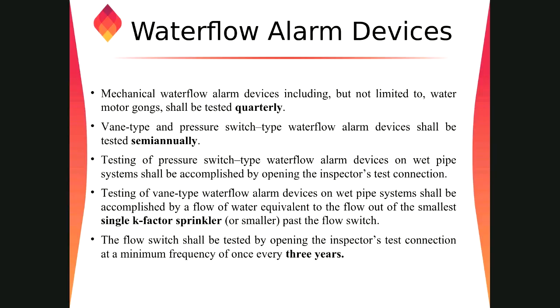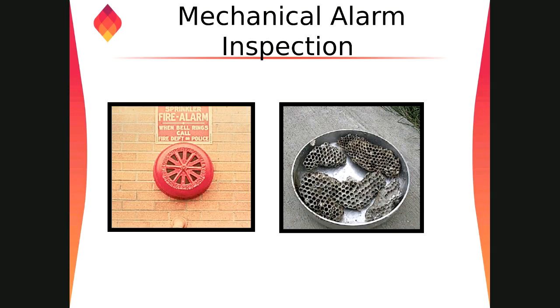We have to check the mechanical water flow devices, right? The vane type or pressure switch, if it is activated correctly. Look at this one, right? If you are inspecting, this is a mechanical alarm bell for the sound, but it looks like this is not working. This has not been working for so many times.